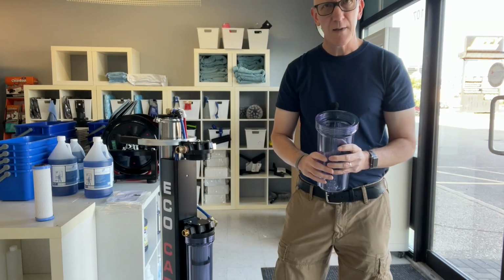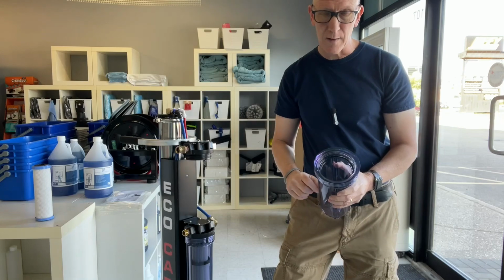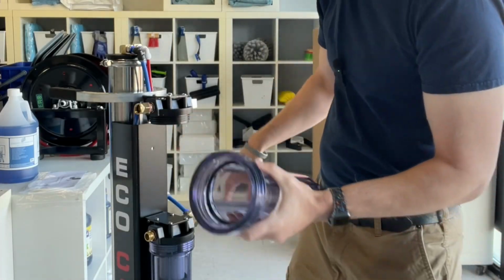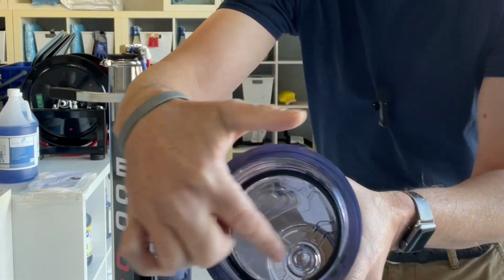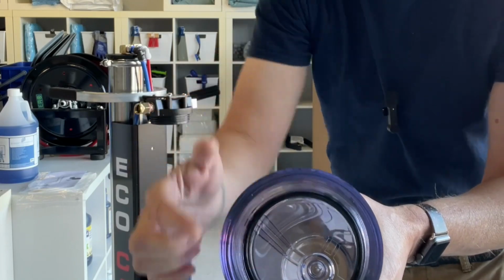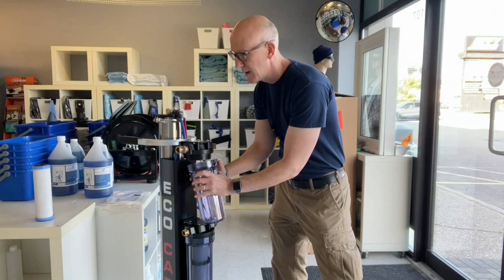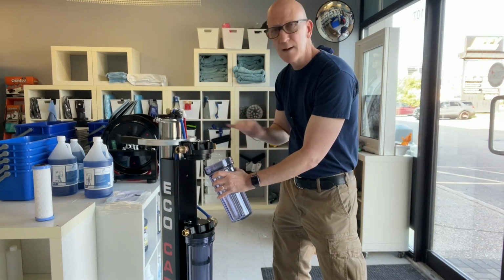Only problem is they didn't notice that when they tossed out that water, they tossed out something very important. On the inside of housings, whether it be a pre-filter or a DI, there's usually either on top or deeper inside a nice rubber O-ring. It's that O-ring that makes sure that when you tighten this by hand after changing out a filter, this thing is airtight and watertight.